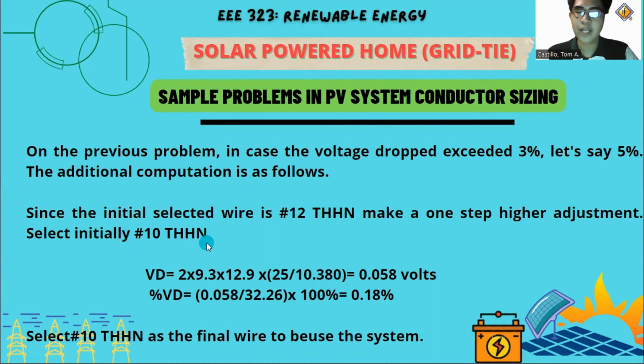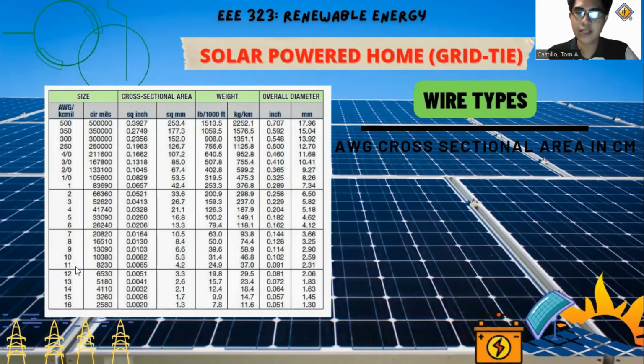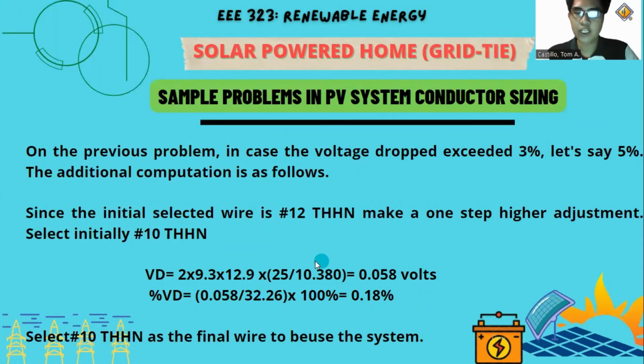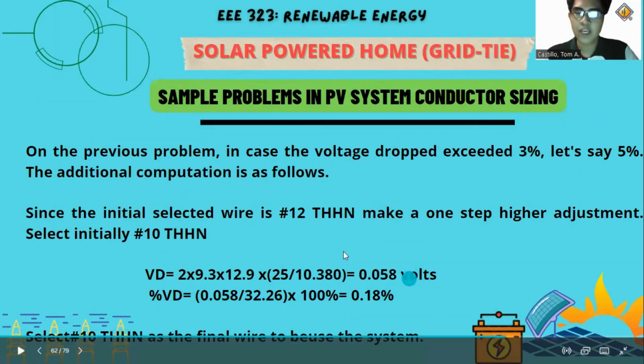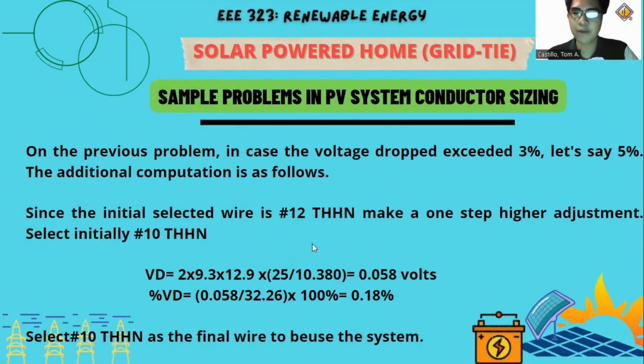So, ngayon, dahil nga binago natin yung size ng wire natin, mababago rin yung area. So, ano ba yung area natin ngayon? So, dahil 10 na yung size ng wire natin, ang area natin is magiging 10,380. Kaya, ang magiging voltage drop natin is 0.058 volts. Ang magiging percent ng voltage drop natin is 0.18%, which is less than sa percent ng voltage drop kapag ginamit natin yung number 12, which is 2.85%.